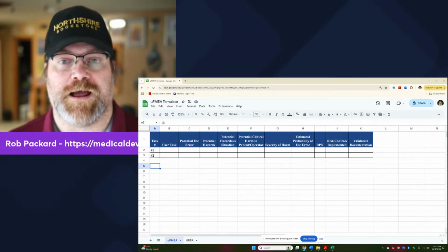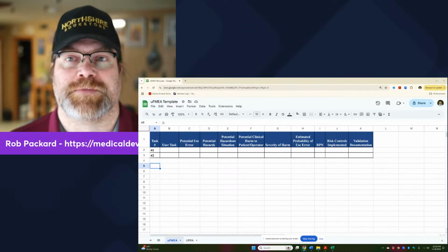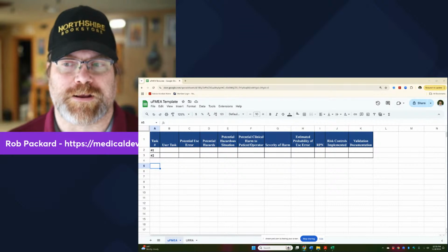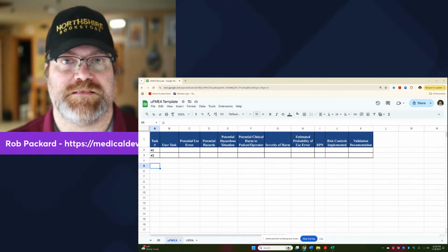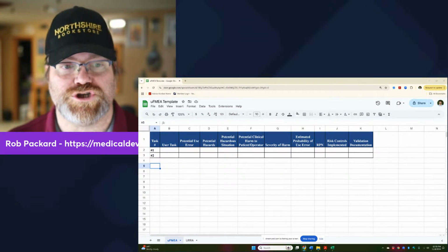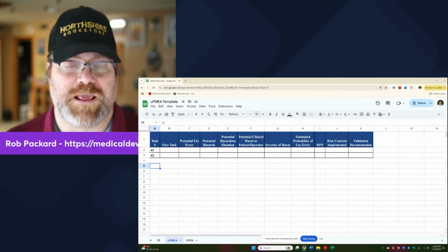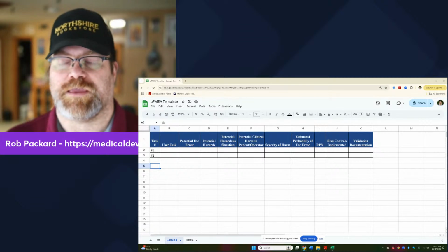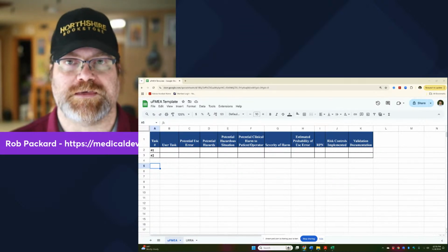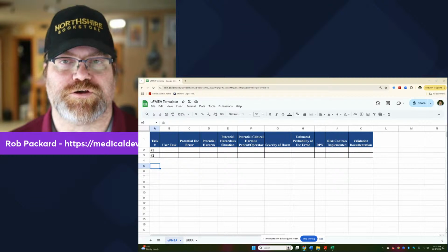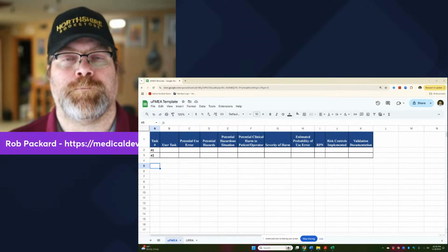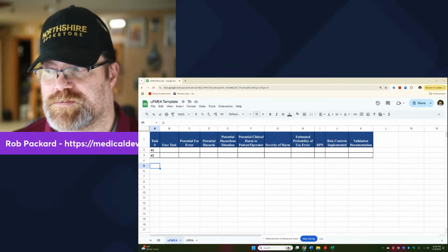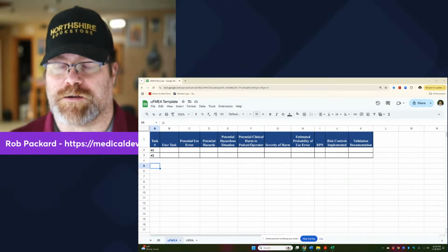Most people will realize their mistake before they make it, and we'll call it a near miss or a difficulty performing the task, but they'll perform it correctly. Sometimes the device is designed to give us an error message, so we correct ourselves without any harm occurring. So there's a lot of different possible scenarios where it isn't going to be 100% worst case scenario; we're going to have some lesser event that's going to occur. But we prioritize the implementation of our risk controls, or some people will say mitigations, and we'll talk about that shortly.